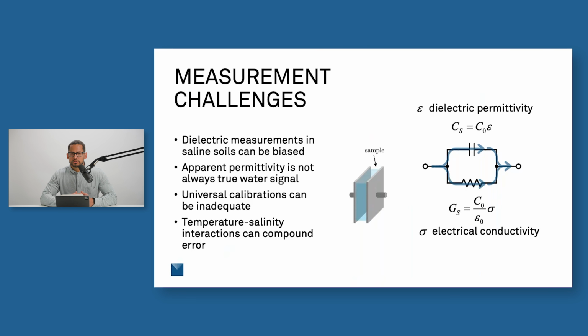Other challenges with measuring soil moisture is that apparent permittivity is not always a true water signal. And this again goes back to the issue with the lossiness of both clays and the conductive soil with the salts. Other challenges is that universal calibrations can also be inadequate at times, depending on some other challenges with your soil. We'll talk a little more about the conductivity challenges, but we also know that depending on the frequency that your probe operates and some of these other things, you can struggle with using a universal calibration to get good water content measurements. And so sometimes you have to do soil specific calibrations and things like that. And some other things that we've seen is that temperature and salinity interactions can also compound error as well. So these are all challenges that we're aware of in making these measurements.